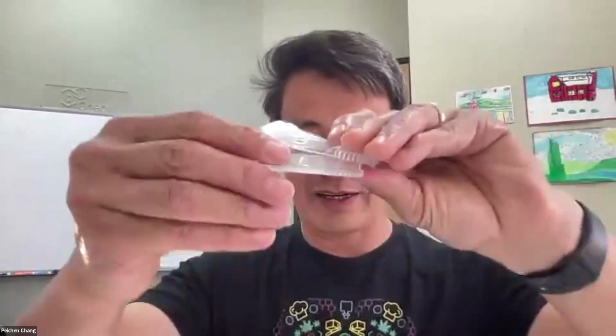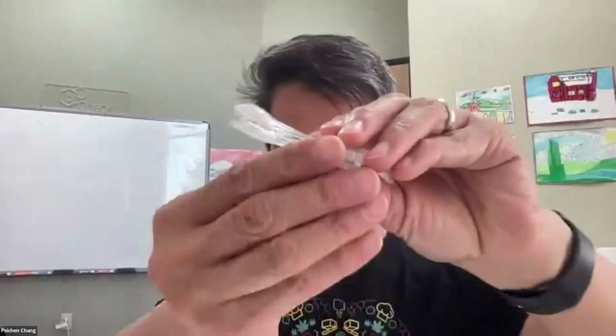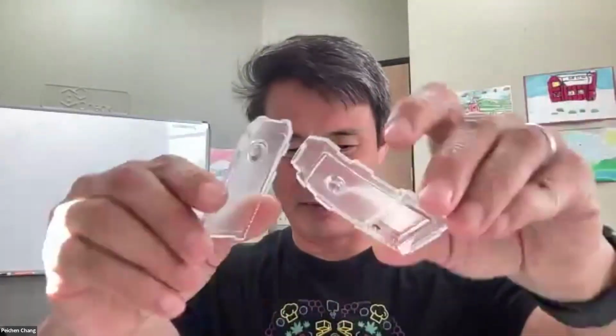With regards to the tray, always please hand wash the tray. Simple Dawn dish soap will do. I want to show you something real quick here. This is a tray where somebody stuck it in a dishwasher. You can see it's pretty well warped. Unfortunately, this is no longer salvageable, so we had to take the tCheck back and recalibrate it. So please hand wash the tray.